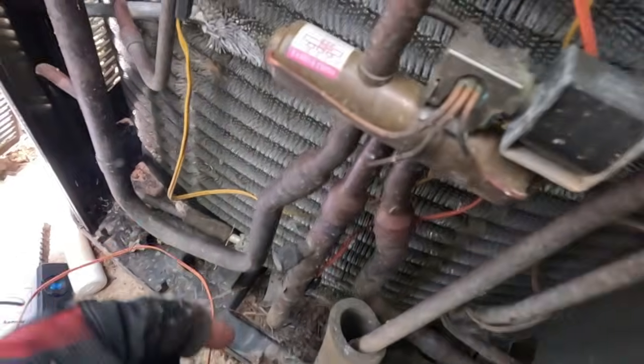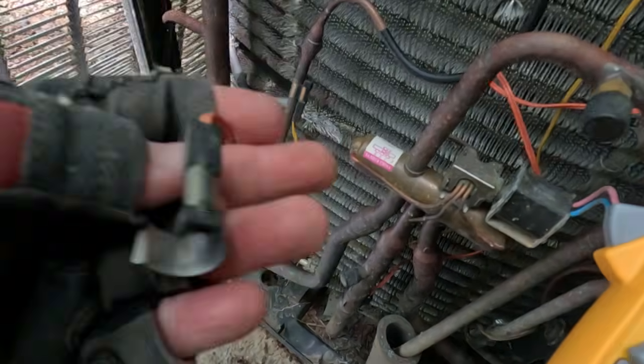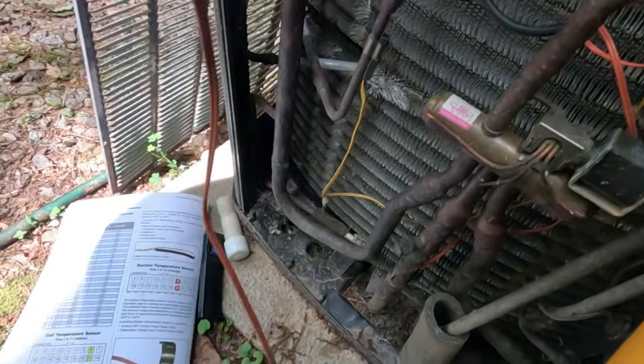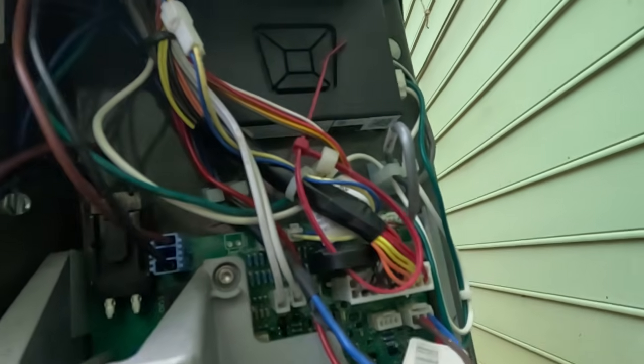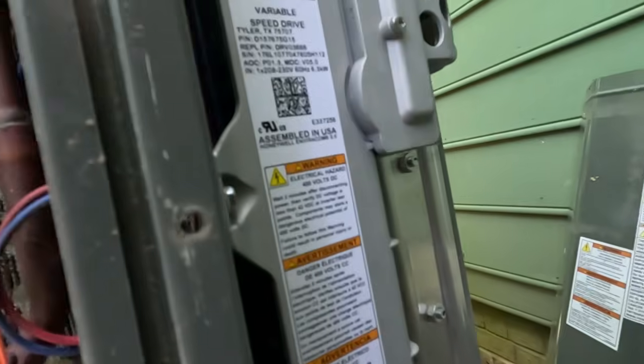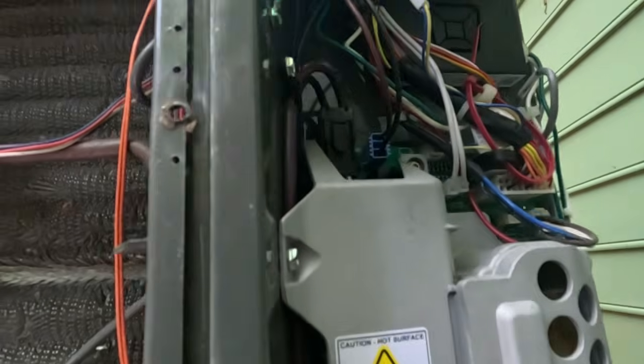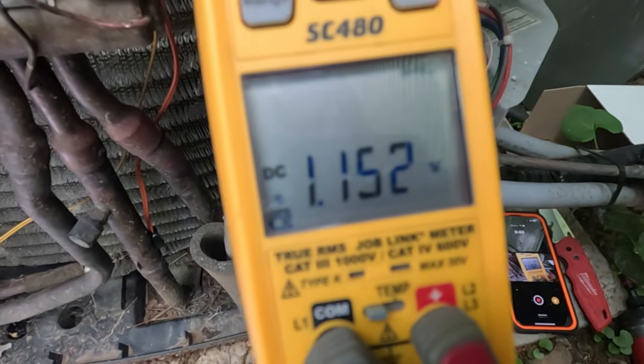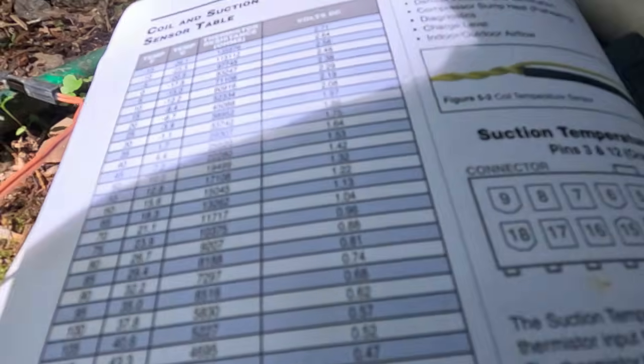Alright, so we have our new sensor mounted and snapped on. Here's the old one. I'm going to double check this one now. Go right in here. I'm going to grab the right leads. Go right in here to our orange to orange right there. And we are now at 1.15 DC. 1.15 DC now. Is telling us it's about 65 degrees, and it's 64 out here, so problem fixed.